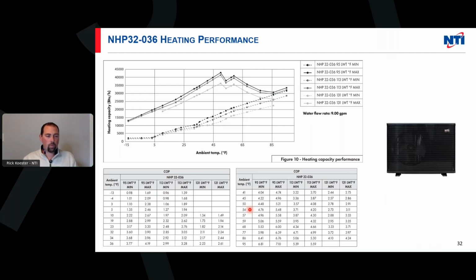And then at the bottom here, I threw in the COP charts, right? If we're designing around a certain COP, we can pick that COP if we know what the most efficient fuel is at that point, and we can look at the outdoor temperatures and see the performance we would get out of the machine. This is going to be very common when designing around hybrid type systems. If we have a fossil fuel machine and the heat pump, and they're both integrated together, we can pick and choose at what water temps and outdoor temps we want to switch over to maybe an auxiliary heater and switch between basically inputs, which is really cool.